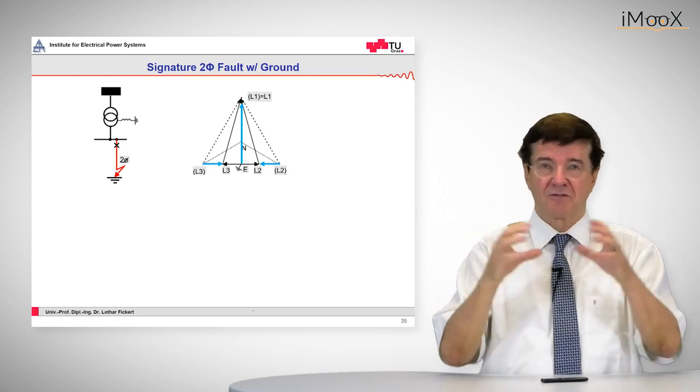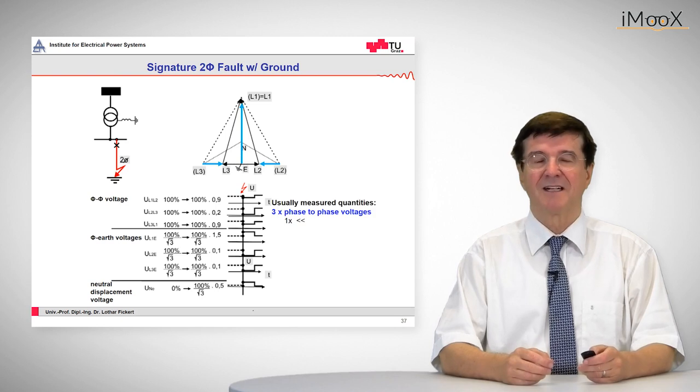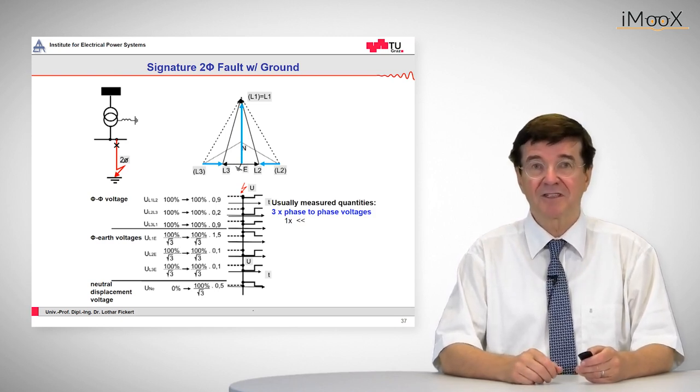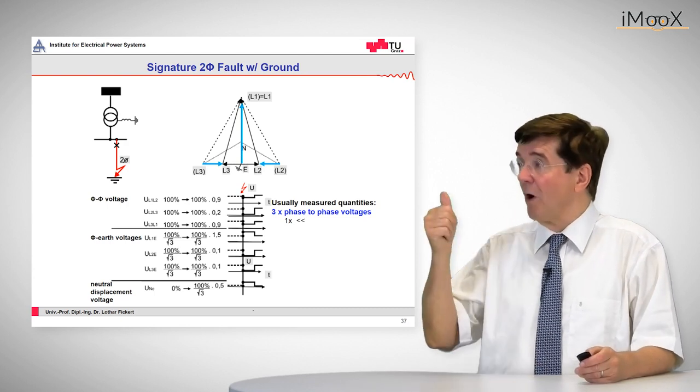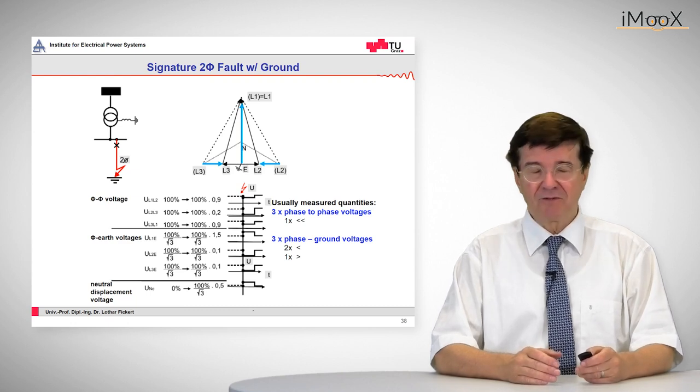Again we start with the appearance of the fault and now we can see that the two phase voltages collapse versus ground. And this pattern is repeated in the traces. So again we start with the first set of traces, which is the phase-to-phase voltages. Here we see that one phase-to-phase voltage collapses.